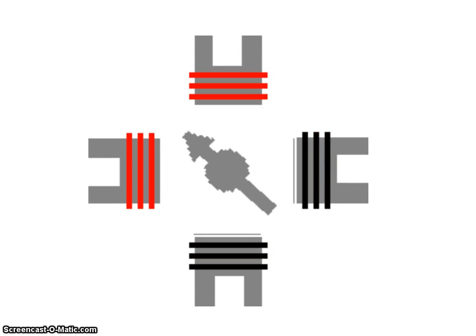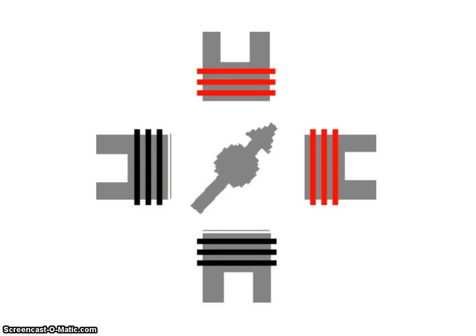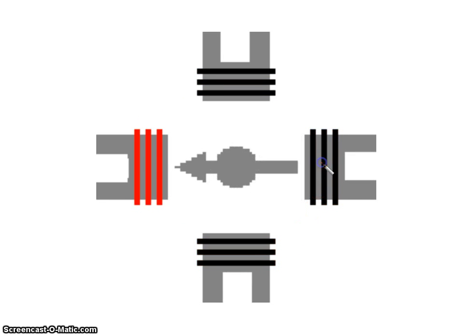So there we have it, rotating around stopping in between the poles. And to take that one step further, if you had the right controller with a four pole motor you could stop that rotor in any of the eight positions that you see here. The other thing to note is depending on the sequence it can rotate in opposite direction.